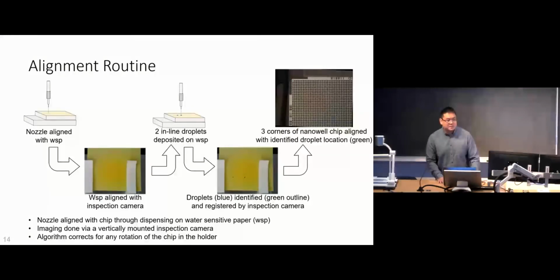Then 2 droplets dispensed 5 millimeters apart are dispensed on the water-sensitive paper, leaving a mark, which can then be identified by our inspection camera. As shown here, the water leaves a mark of blue and the camera identifies the droplet outline in green. Next, the position of the droplets, where the droplets are being dispensed into, is then used to align the 3 corners of the nanowell chip.